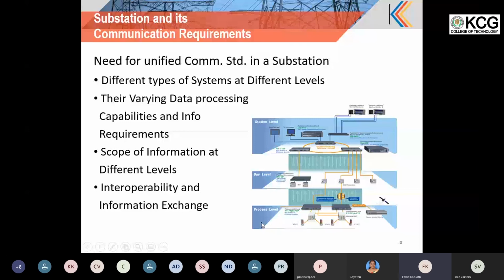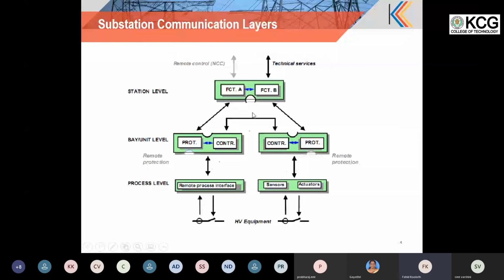Moving on to substation communication layers again. The process level has multiple sensors, actuators and remote process interfaces. The bay level has protection and control equipment. Then the station level has HMI, alarms and other functionality embedded. So these are the major three levels addressed in 61850.